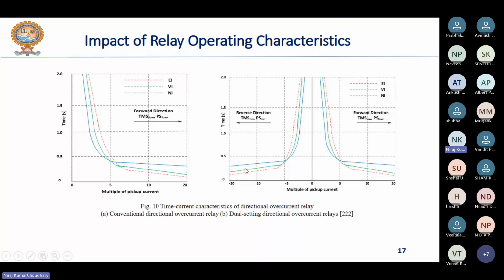Now, in figure B, you can see this is a dual setting directional overcurrent relay. The first one was the conventional directional overcurrent relay, which will operate only in a particular direction of fault current, either forward or reverse. But this is one of the user defined relay characteristics, dual setting relays. From the name itself, dual setting means it has two settings, a pair of settings. One is for the forward direction and another for the reverse direction, right?